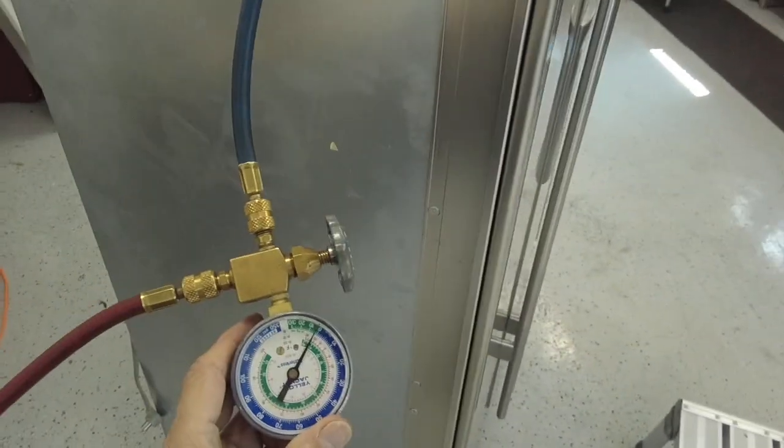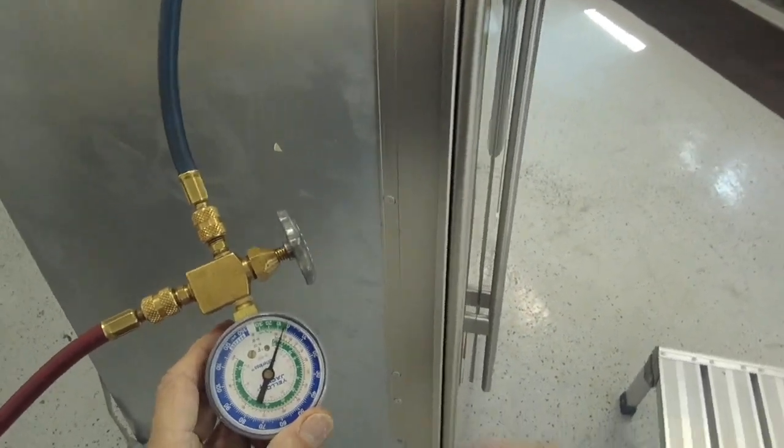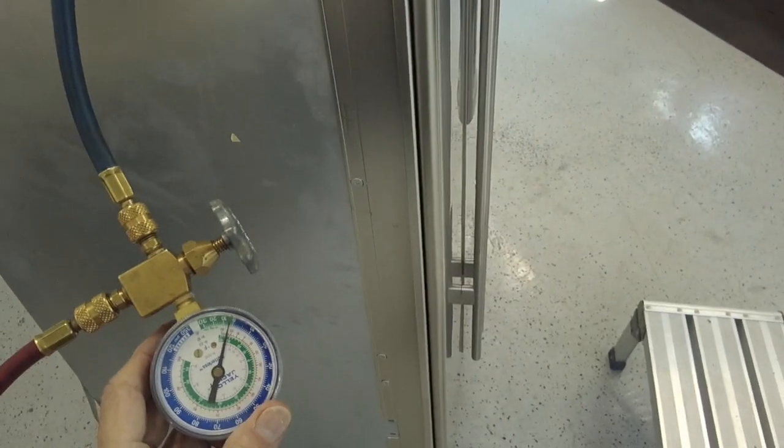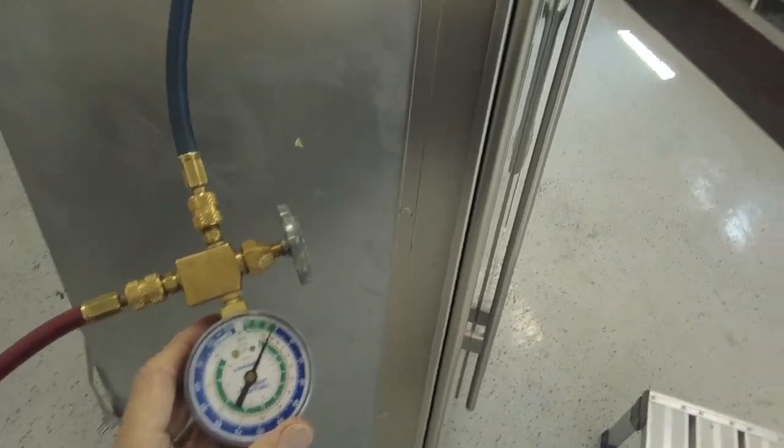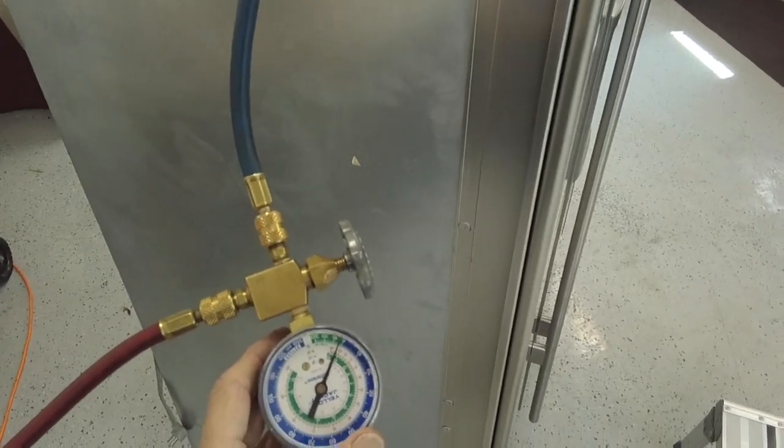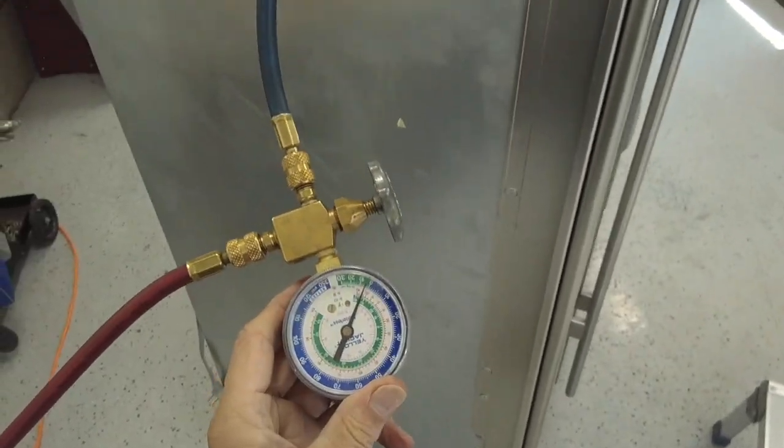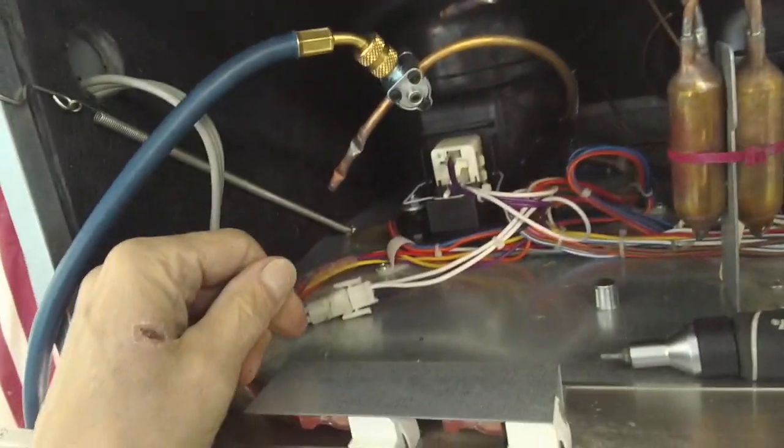It's recommended at least 10 inches in a vacuum. 10 inches of mercury is the proper terminology. You want to make sure you're in a vacuum before you open up the system so as not to ventilate any refrigerant into the air. It's illegal. It's not right.